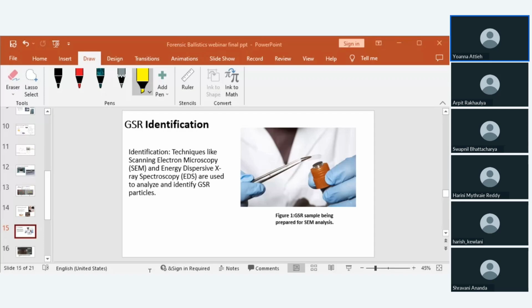It uses a cerium hexaboride, known as CeB6, solid-state electron source, which provides brighter and more stable imaging than traditional sources. This one, guys, is well suited for automated SEM and EDS analysis, delivering high-resolution imaging with unparalleled stability.